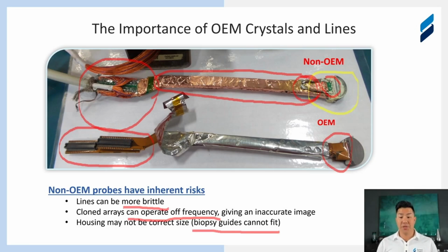And now the healthcare facility is stuck with this clone transducer that doesn't do what it's supposed to. You may have gotten a good deal on it once, but it keeps getting reserviced or needs to be constantly replaced. And that frequency means a new service call every single time, with all the soft and administrative costs that go into sending it out to a repair company, replacing it, and absorbing the time of procurement and the engineers. Most of all, you're always going to that site, and it could be a lot of windshield time if you have multiple sites, or the end user just gets really frustrated because they keep failing over and over for no apparent reason.